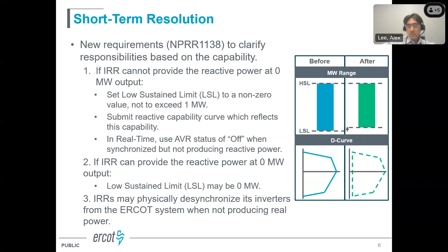So what has been the impact of these new requirements? The main goal has been to minimize the reactive power and voltage oscillations on the system caused by the current equipment limitations. Because whenever the oscillations happen at a very low megawatt output, the voltage on the transmission system can swing several kV, as I showed you a couple of slides ago.